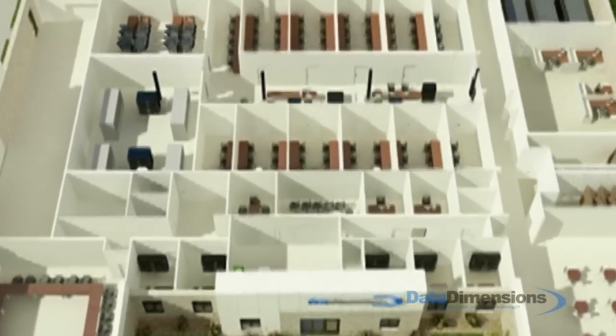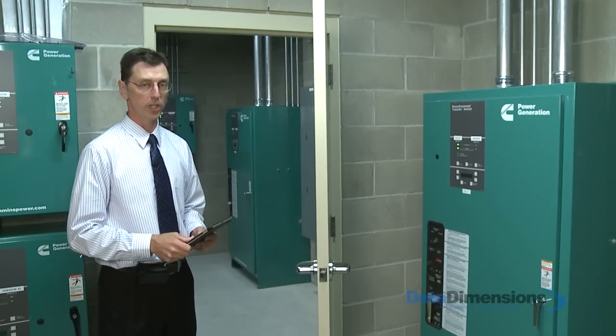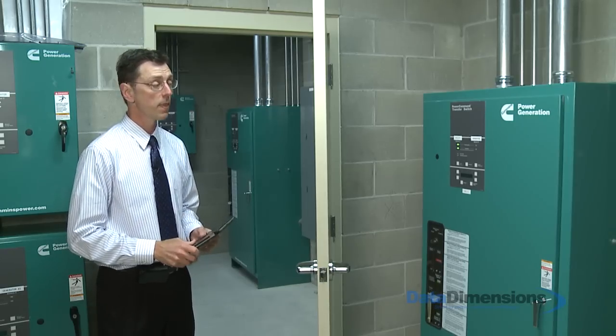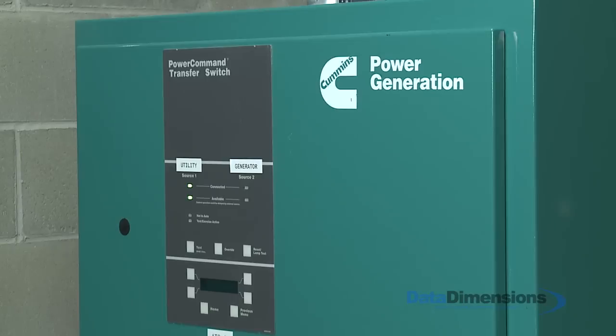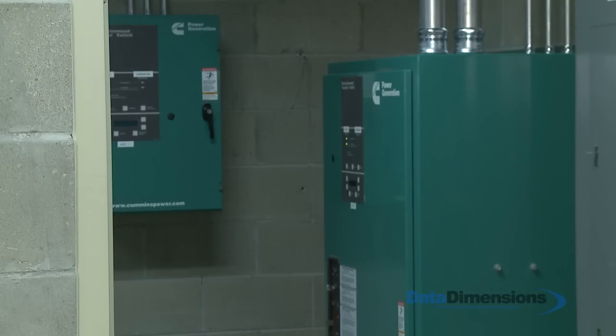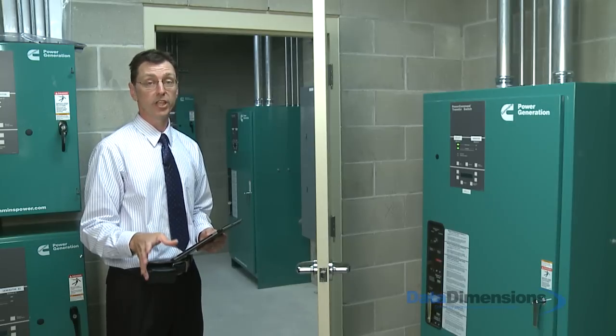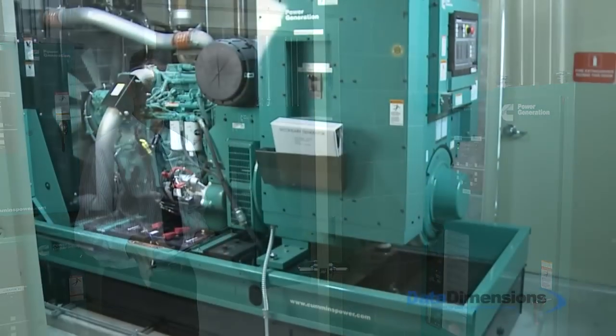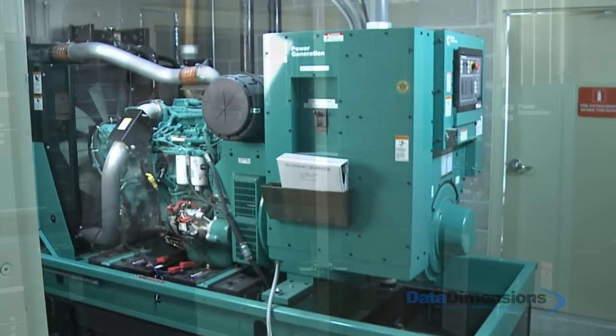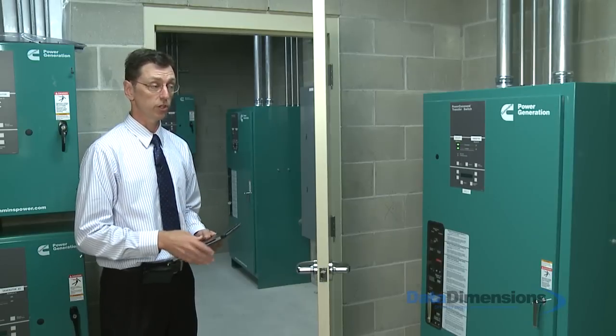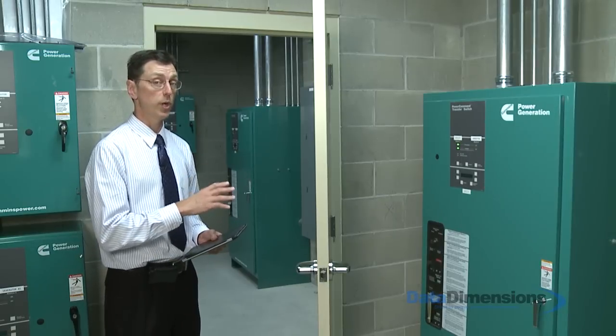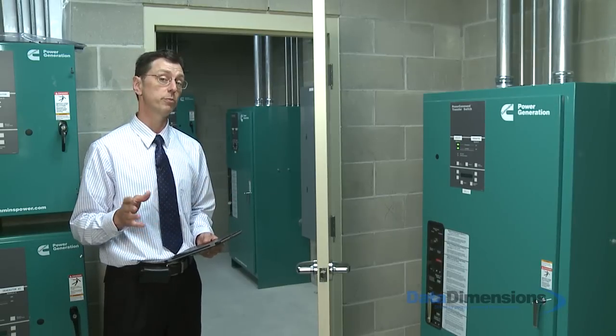Here we are on the ground floor of the facility in a dedicated electrical space for the data center itself. We have transfer switch A and transfer switch B, which are dedicated to the two 250 kilowatt generators that we just left down in the basement. These control those generators in the event of a power failure, switching over from lead and lag, as well as in the event of an interruption of power from the utility.